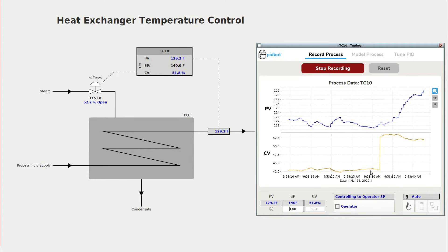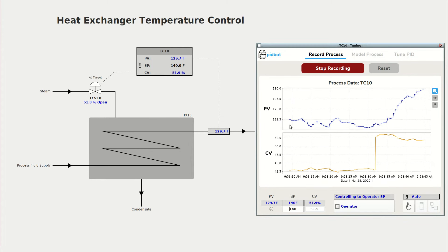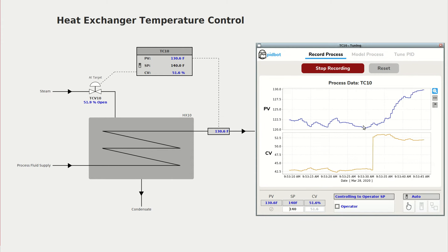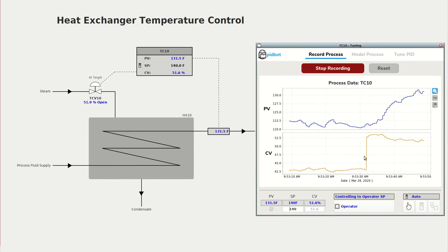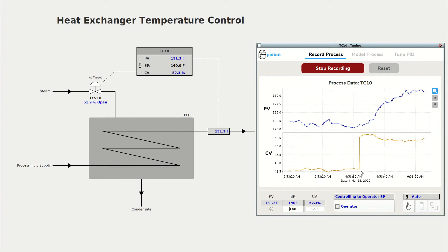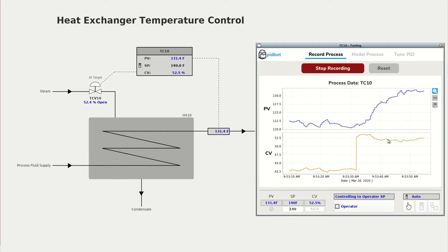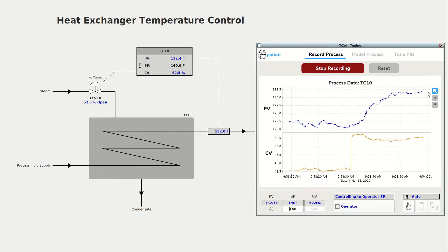In our case we had a little bit of noise in temperature data but the process itself was steady, and then we generated a nice clear change in CV that generated a nice clear response in PV.